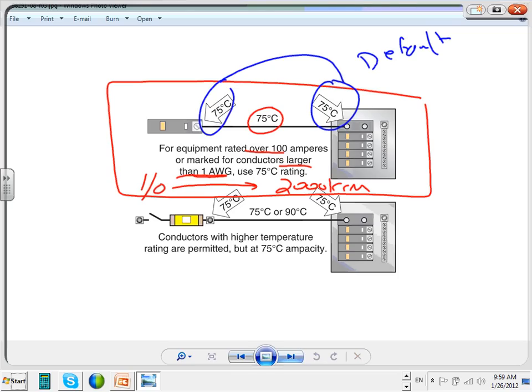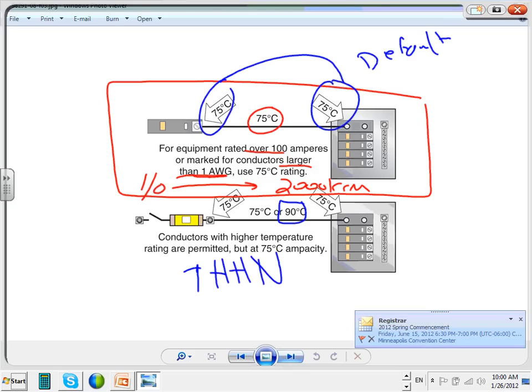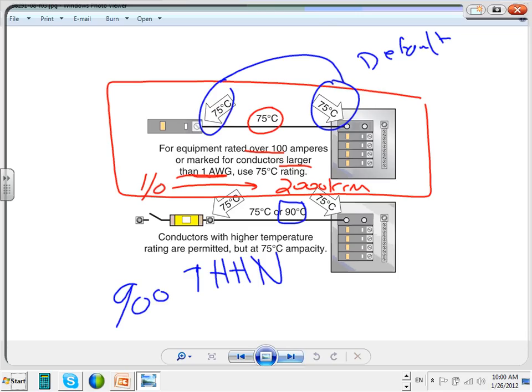And what they're telling us, guys, is you can have conductors with higher temperature ratings. Most of the time we use THHN. This is rated for 90 degrees, right? We use it here, but we can't size based on 90 degrees. What do we use 90 degrees for? Can somebody remind me? Thank you. Only for derating. So the 90 degrees Celsius is for derating.